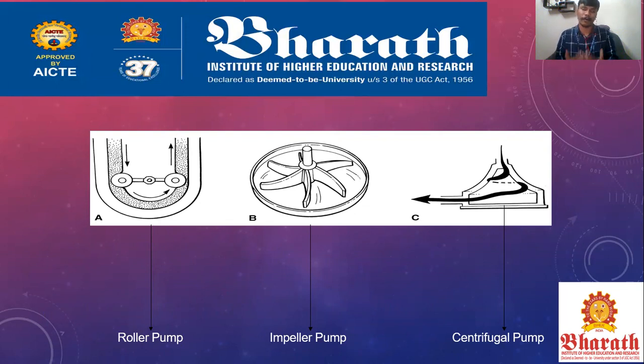And the centrifugal pump, we already saw, is a pump constructed with a cone. That cone is rapidly rotated and centrifugal force is produced. The centrifugal force will drive the blood feed forward. Positive 900 Hg of pressure will be applied, but in response it will provide only 400 to 500 of negative pressure, which will drive the blood without any collision or lag.